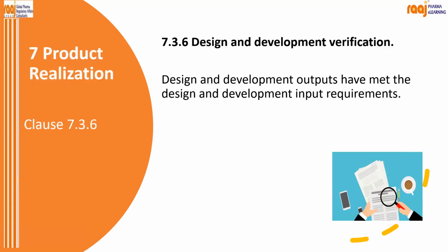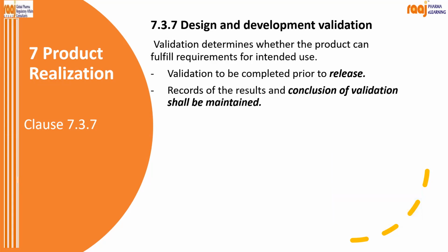Then it has to be verified. Whatever input you are given, whether the output is correct or not has to be verified. Test versus standard is also verified; it has to be tested. Under clinical, you have to prove that it is clinically safe. Analytically, you have to say that it is equivalent to 100%, giving results as per the predicate device. So, test versus standard reference versus our test.